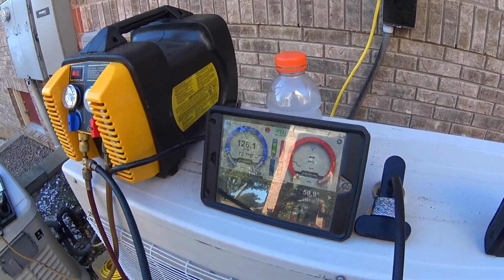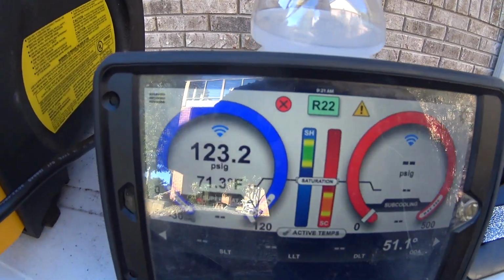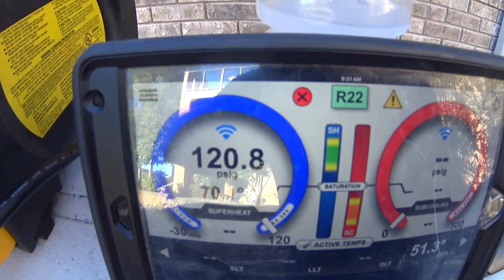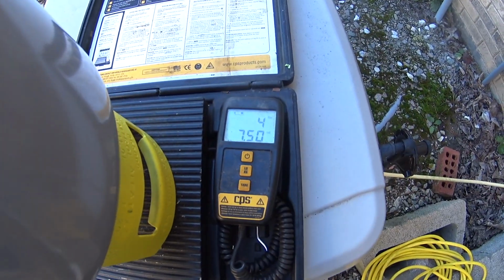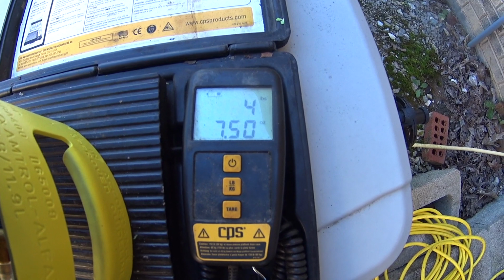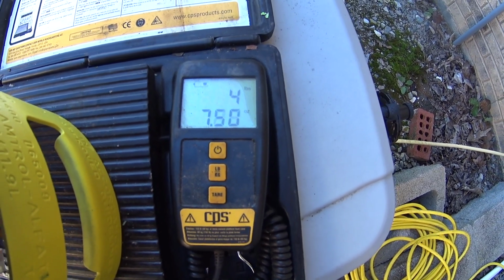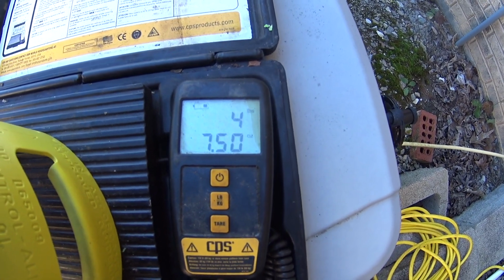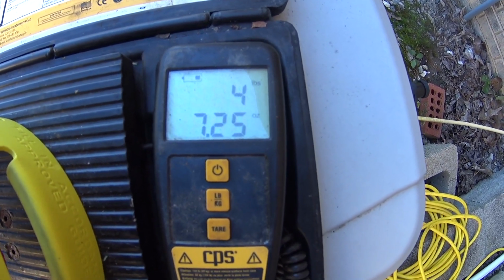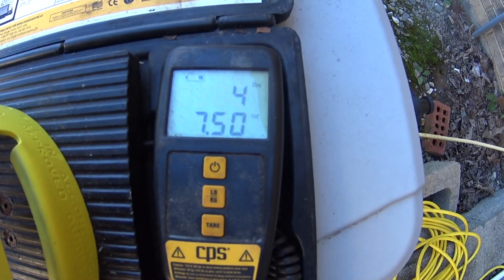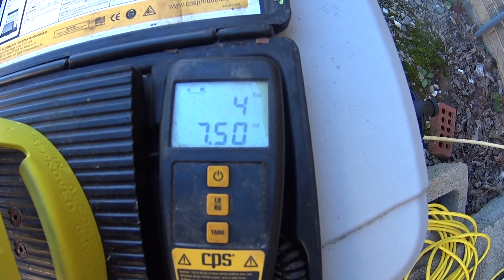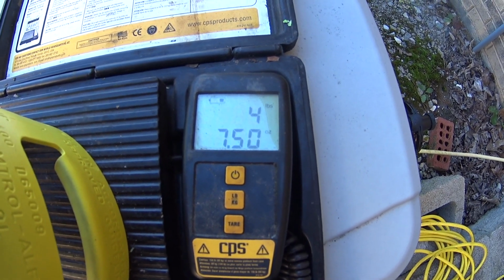And we'll check in when we get pulled down. Well, it is recovered down to a negative PSI on the gauge, and we've got about 4.5 pounds. And the kicker is that this unit holds nearly 12 pounds. So we definitely have a significant leak.